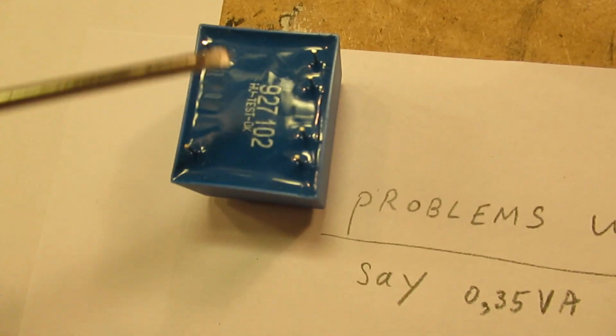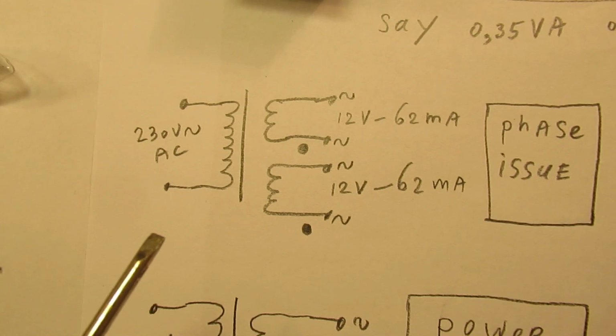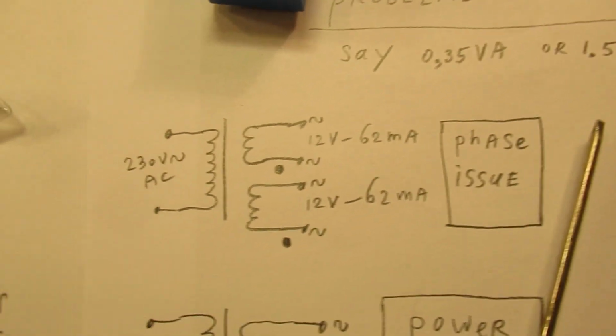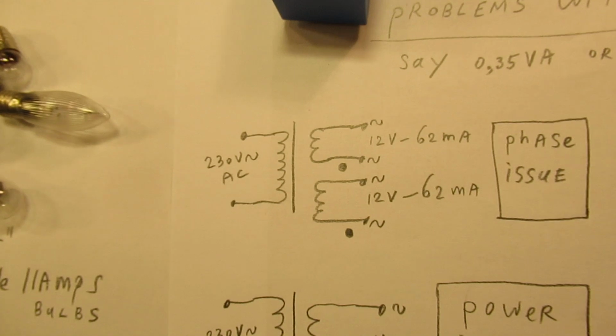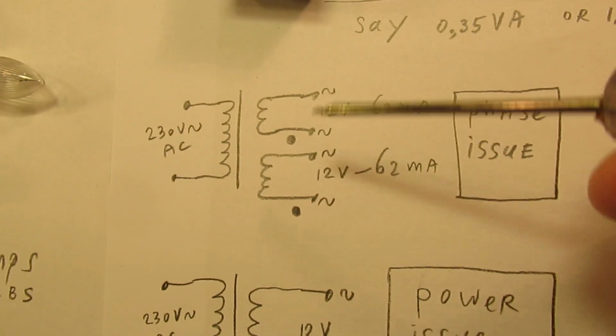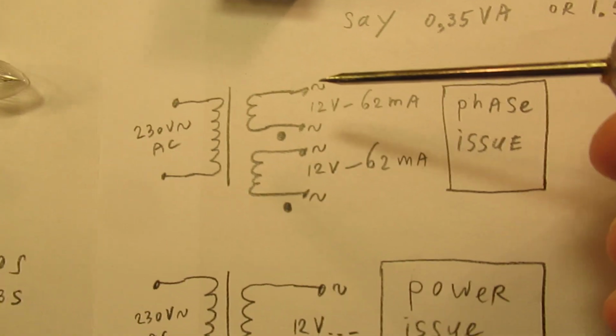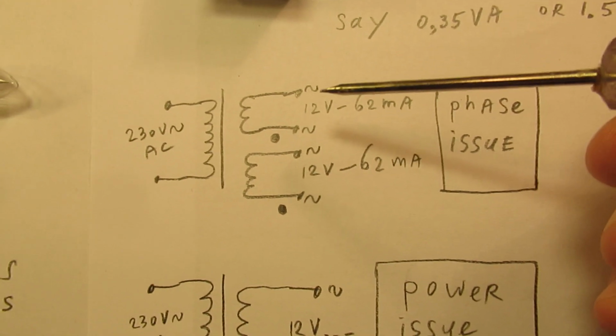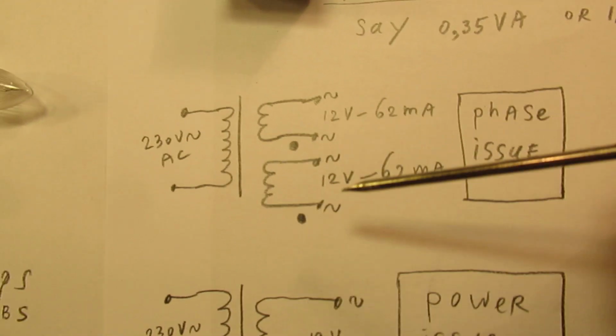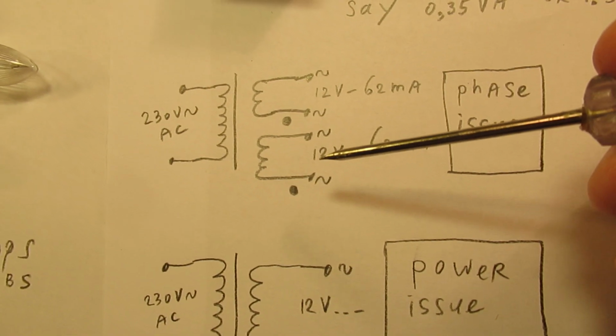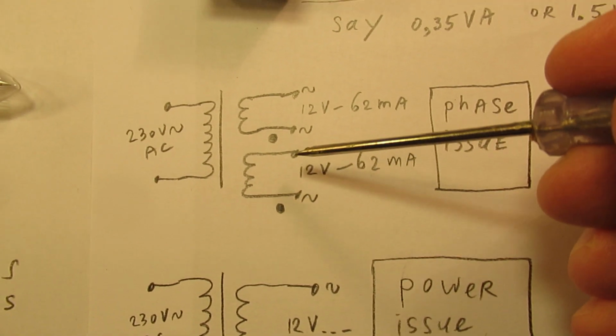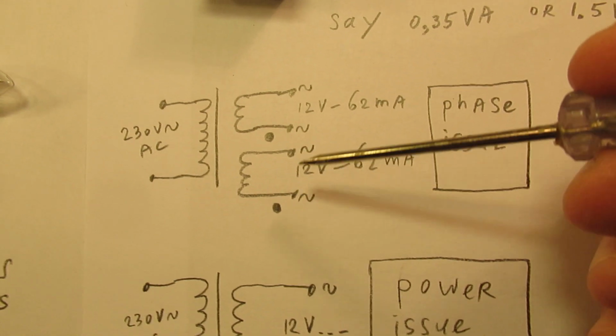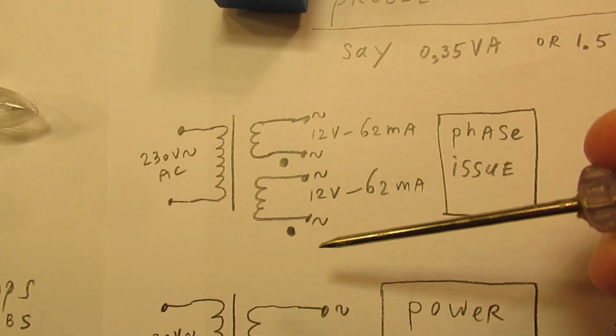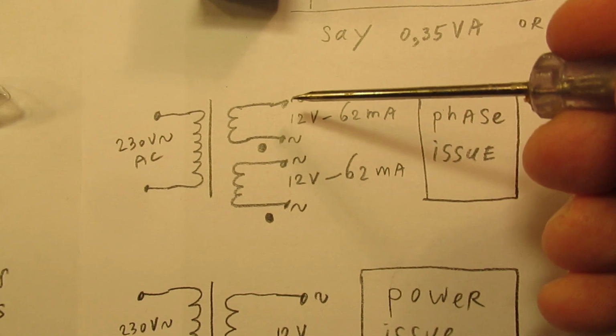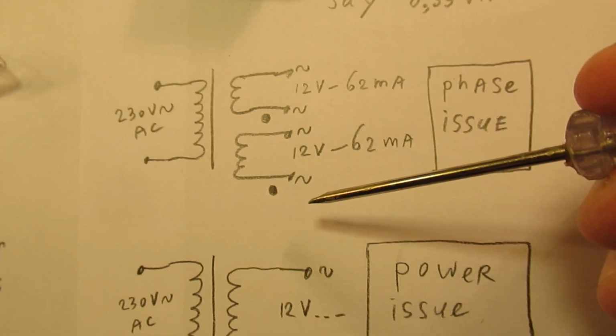You see one winding and another winding, and here is the schematic, and the phase issue tells us that when you don't make the proper connections here, and when you want to take 24 volts out, or even 12 volts out - in a 12 volt situation you have to parallel both windings, and in a 24 volt situation you have to set these windings in series.